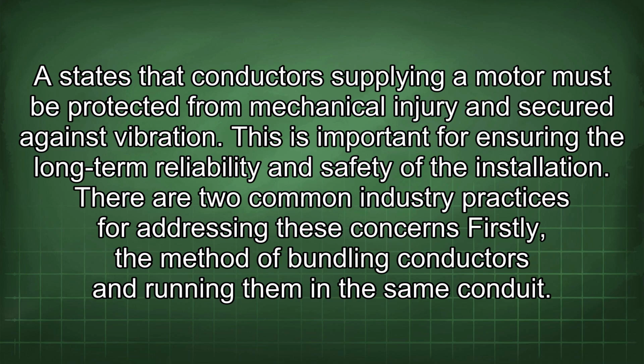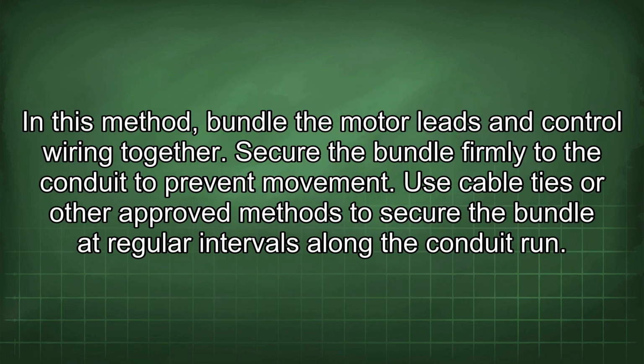Firstly, the method of bundling conductors and running them in the same conduit. In this method, bundle the motor leads and control wiring together. Secure the bundle firmly to the conduit to prevent movement. Use cable ties or other approved methods to secure the bundle at regular intervals along the conduit run.